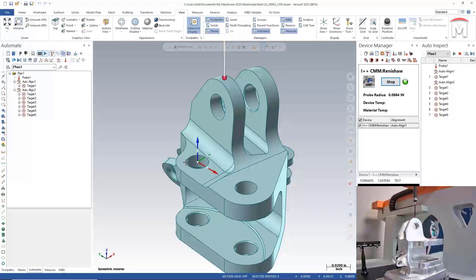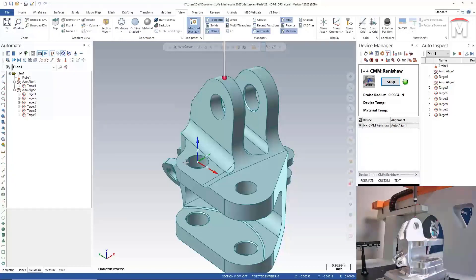As the inspection plan is built, you'll notice the auto-inspect manager on the right side of the screen starts to populate with the objects created in automate. The difference between these two is auto-inspect is simply a playlist, and automate is where you actually create the inspection plan. We'll go ahead and run what we've created so far. Similar to the behavior of the manual auto-align performed earlier, the user will be guided on the first point. The difference now is the CMM will run the following measurements in automated mode.